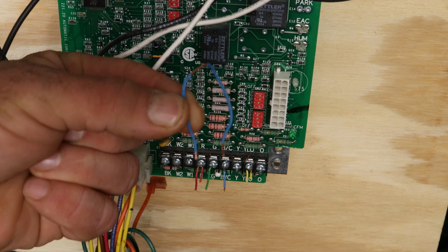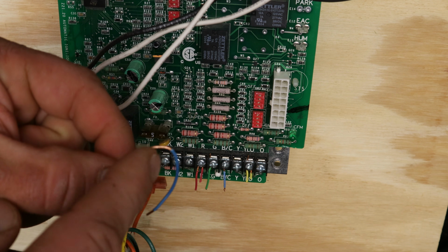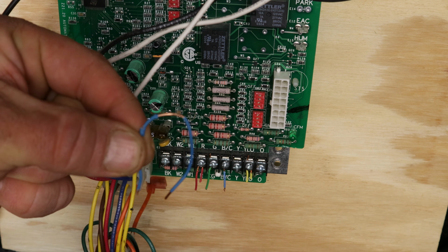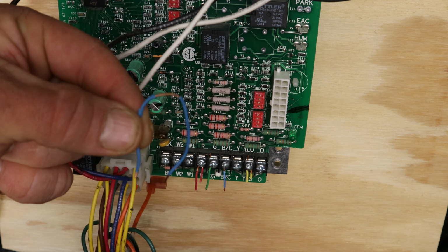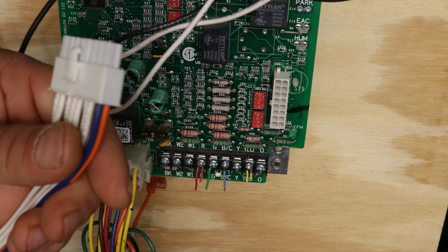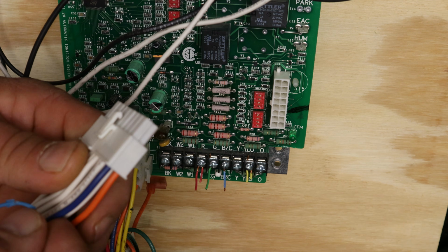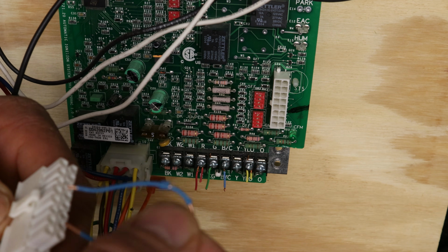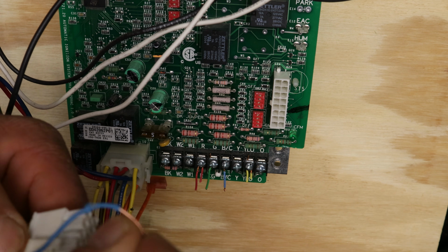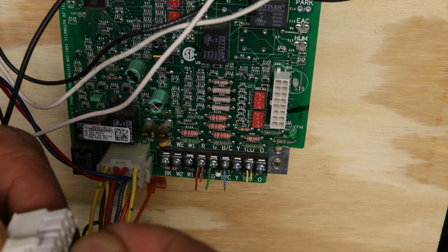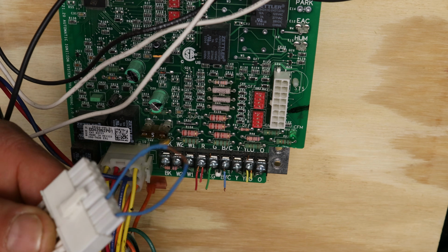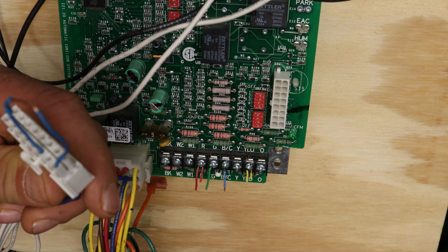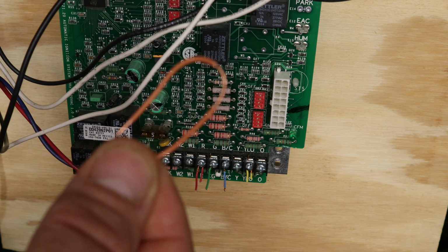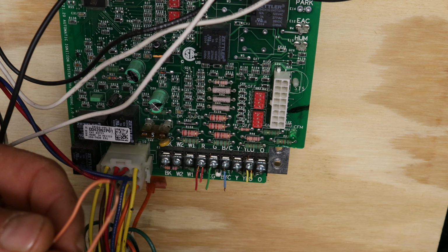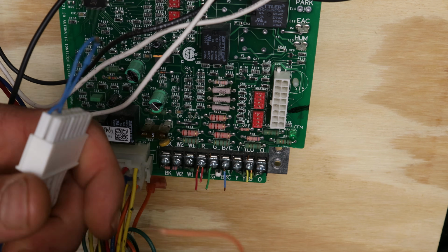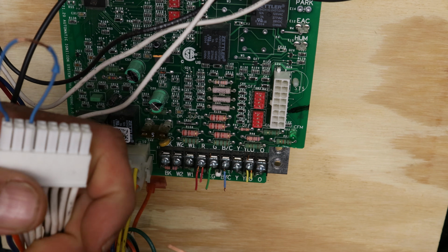Now I'm going to take a little piece of thermostat wire. I have a little bare spot that I put in there so I can attach alligator clips to it. And what we want to do is we want to go from pin 1, which is where that blue wire is, to pin 3. So I'm just going to throw that jumper right in there to pins 1 and 3. Then I'm going to take another jumper, same thing, and I'm going to jumper between pins 15 and 12.